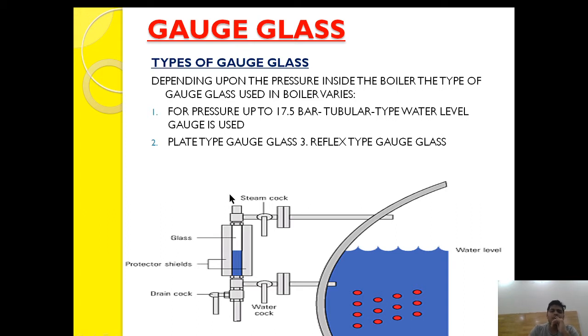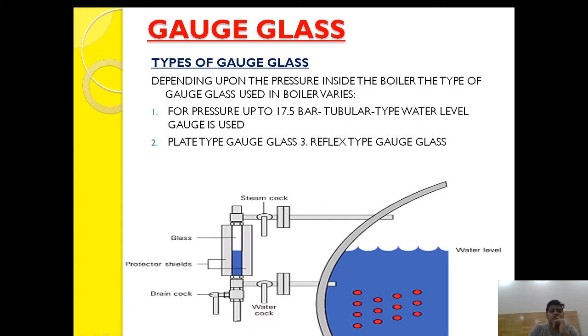So let's start the video on the types of gauge glass. The gauge glass can be defined in three parts: one is the tubular type, second is the plate type, and third is the reflex type. The reflex type gauge glass is a type of plate type gauge glass but with some restrictions in construction. For pressures up to 17.5 bar — that is, medium pressure boilers — the tubular type gauge glass is used.